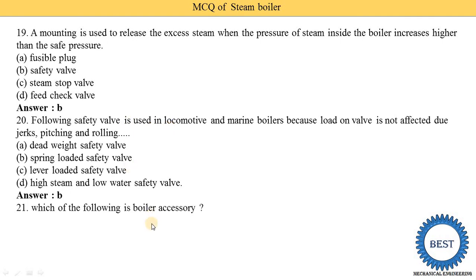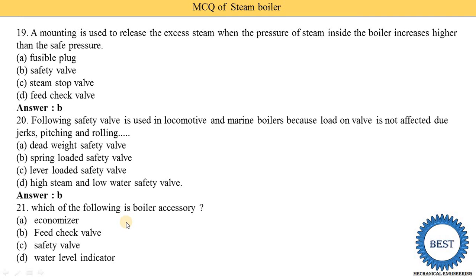Which of the following is a boiler accessory? Options are economizer, feed check valve, safety valve, and water level indicator. The economizer is an accessory; the other three are mountings. There are seven types of accessories: feed pump, injector, economizer, air pre-heater, super-heater, steam separator, and steam trap. The correct answer is economizer.